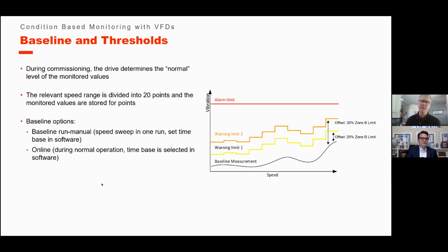But you have a manual run. Now, I made the example of 500 to 1,000 RPM. If we do a manual run, we actually do a sweep from 500 to 1,000 RPM over a predefined period of time, but we do it all at once. Sometimes that's not hard to do if you have a fan or a pump. But sometimes it's very difficult if you have a conveyor or a more complicated machine. You can't always run through that speed range without creating problems. So the second choice is what we call an online type of baseline run. That's the software sitting in the background, gathering all the points over a period of time. Now that period of time can be 2 hours all the way up to 6 months. So you have a lot of versatility with this.